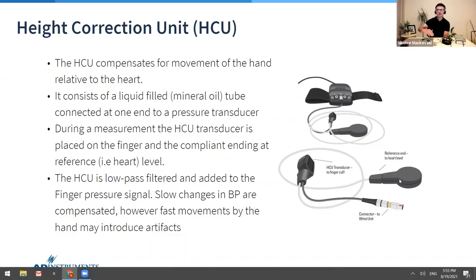Basically, as we move our arms, the HCU applies a low pass filter, and that's added to the finger pressure. Therefore, any slow changes we see are compensated. That's something I'm going to demonstrate later on in the webinar when I do some of these movements. You'll see in one channel the raw finger pressure, which will drop when I move my arm above my head, whereas the HCU pressure will be the compensated pressure. That pressure will be similar to what it was when my hand was around the table here.